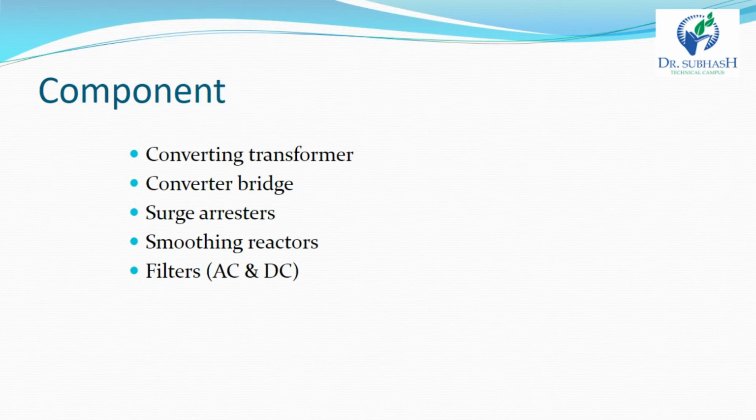Now the converter transformer. The converter transformer converts the AC network to DC network and DC network to AC network. They have two sets of three-phase winding. The AC side winding is connected to the AC bus bar and the valve side winding is connected to the valve bridge. These windings are connected in star for one transformer and delta for the other. The AC side windings of the two three-phase transformers are connected in star with their neutral grounded. The valve side transformer winding is designed to withstand alternating voltage and direct voltage stress from the valve bridge.